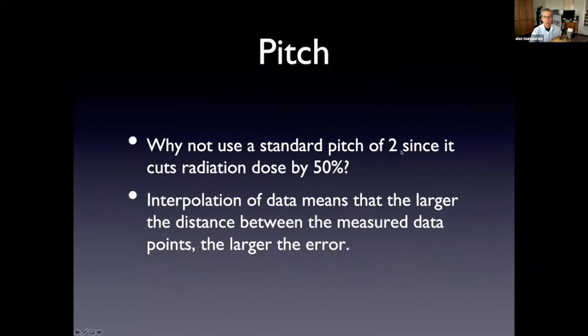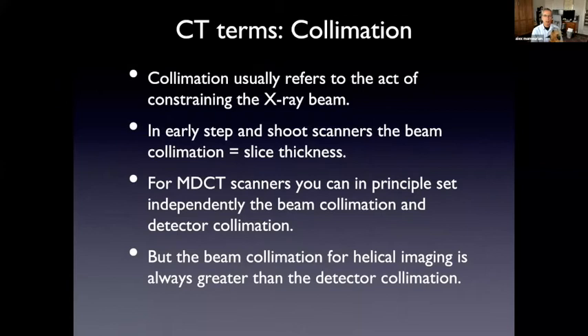So why not use the standard pitch of say two, because we automatically cut radiation dose in half. The problem is that if the distance between the houses are large and the houses are a little different, you're really just estimating what the value of a house is. In the same way, if there's a lot of space in between the data points that you acquire, there's going to be more errors that introduced in the measured data. And you can never really reconstruct at a thin section if you have a high pitch.